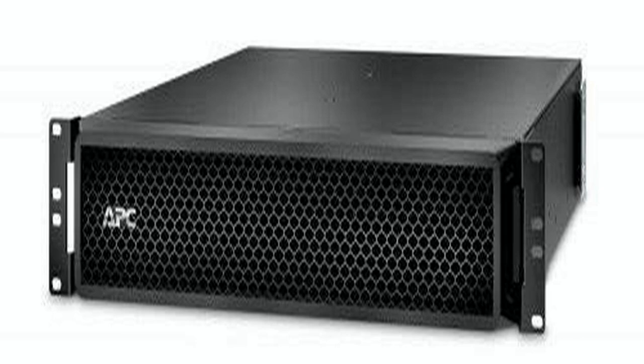Out of the box, the base battery pack gives you roughly 10 minutes of backup at a 50% load. That's enough to trigger a generator start on many sites. But if your load spikes or you need more than a quick pause, you'll have to invest in additional external battery modules. The good news is the modular design makes that upgrade straightforward, but it does mean the initial purchase might not cover the full runtime you anticipate. It's a hidden cost that shows up once you start mapping your actual power consumption versus the UPS's capacity.